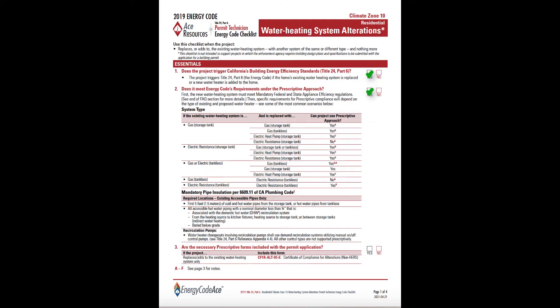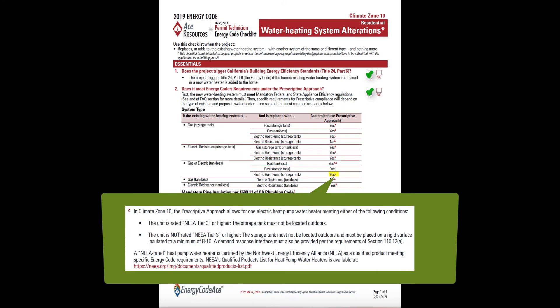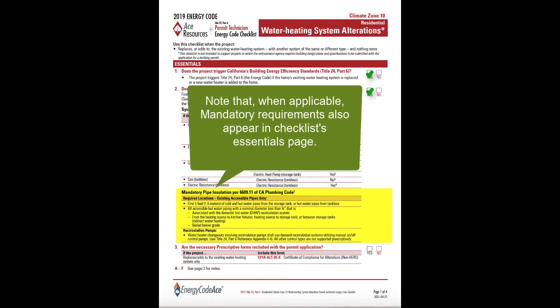A quick consult of footnote C on page 3 shows more information. There are two types of compliant heat pump water heaters under the prescriptive approach, and neither can have its tank located outdoors. When you use your checklists, note that you won't need to read all footnotes, or even most of them — just review any footnotes cited for the specific scenario you are evaluating. When applicable, mandatory requirements can also appear in the checklist's essentials page.